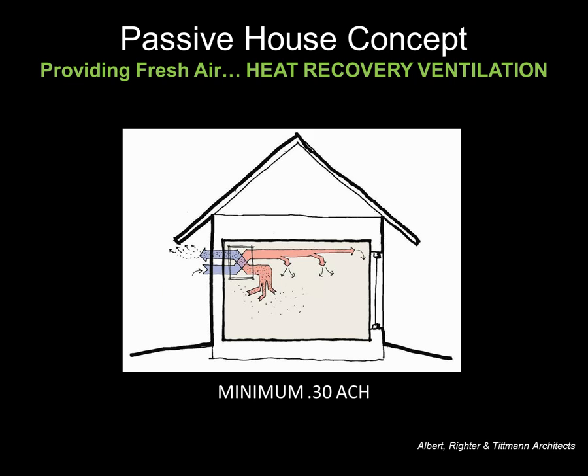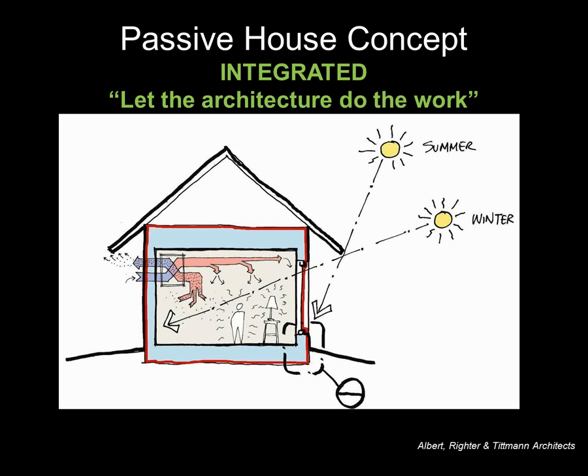The interesting thing about ventilation is we're finding in all the buildings we build, when we test them, even when the contractor is not trying, the blower door is saying that the building needs mechanical ventilation. This was built around the passive house idea, that they realized ventilation wasn't optional, it was necessary. So once you've paid for that equipment, you might as well optimize everything else to dramatically reduce your loads, and then you can really look to this as being the central piece of equipment in the mechanical system. And as I said before, it's an integrated system, and the integration of all these components is what's critical to the success of that.